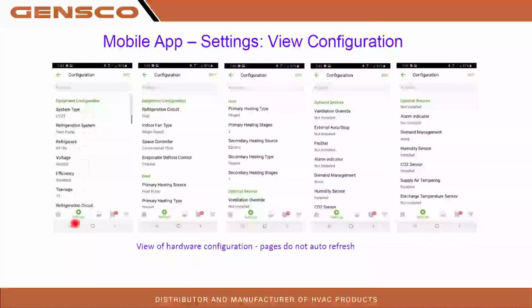Here's what it kind of looks like as you scroll down in configuration. You're going to see multiple space controller. You're going to be able to edit that and put in conventional T-stat. On some of them, they come for zone sensor, so you have to change it from zone sensor to T-stat, because there's a spot on that UC700, the Symbio control board, for the zone sensor. If it doesn't know it's going to be using a conventional thermostat, it won't be looking for it. It's going to be looking for that zone sensor input.